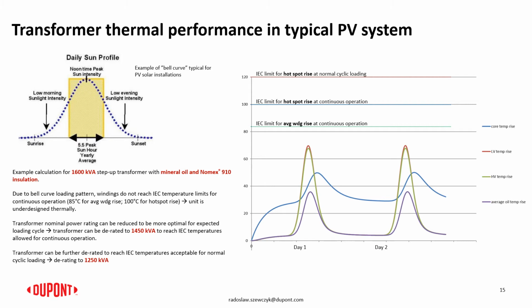And this is the time when the transformer is really loaded, while starting from the morning and then later in the afternoon, the transformer can see less load. What is observed in the temperature records of the transformers is that it is really only a peak loading in the transformer, and taking into consideration the inertia of the transformer weight for getting the temperature during the day, it is observed that the transformer, if it was designed to the maximum power provided from the inverter, might not even get to the typical rated temperature.